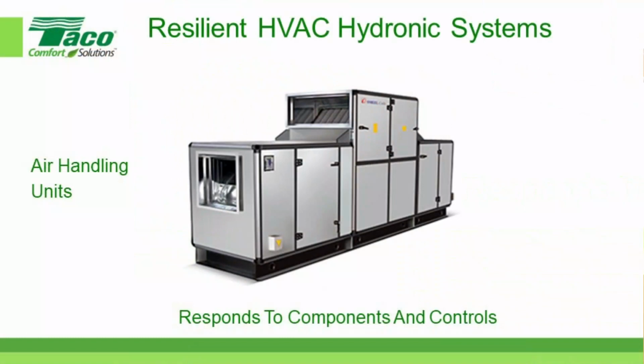Hydronic systems are also connected to air handling units. And I've been around long enough to know that air handling units come in an unlimited combination of pieces and parts and shapes and sizes. I mean, if you can imagine it, you can build an air handling unit to do it. And most of the larger air handling units operate on either chilled water or hot water or a combination of the two. Not exclusively, but a significant number of the larger air handling units, especially the built-up and the custom-built units, use chilled water and hot water, which is a hydronic component.